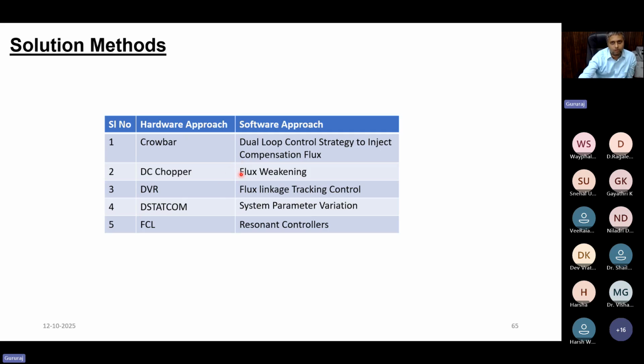And we go for DC chopper, where we connect a switch and a resistor combination at the DC link side. And if there is a shoot up in the DC link voltage, you bypass this. You basically discharge through the resistor by turning on the switch. So the DC chopper is also used. And then we go for dynamic voltage restorer. So here we use an inverter and a transformer at the point of common coupling, in addition to the DFIG machine. So the root cause of all this problem is the dip in voltage, right? Through the support of DVR, we try to restore the voltage so that the entire problem is solved.